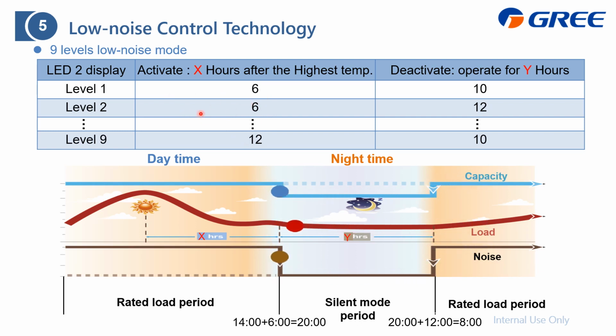Let's say you choose this level 2, and during the daytime, also let's say it will reach the highest outdoor ambient at around 2 p.m. Then after 6 hours, which is this X, it will enter the silent mode period, operate for 12 hours. This is Y, which means during this 12 hours it will be in this silent mode, and then it will be the other day 8 o'clock a.m., and then it will be another cycle for the other day.